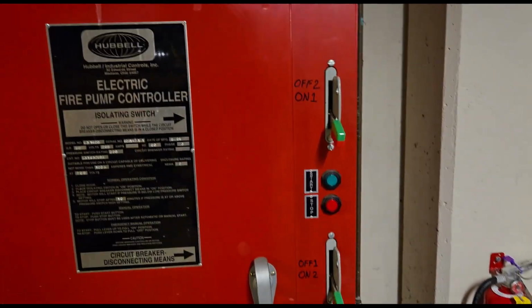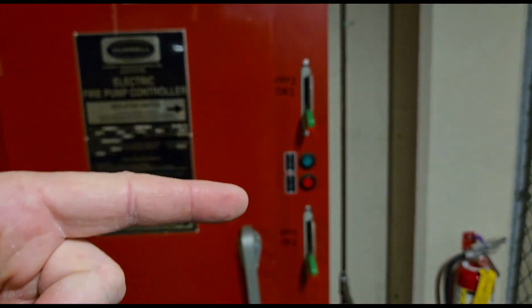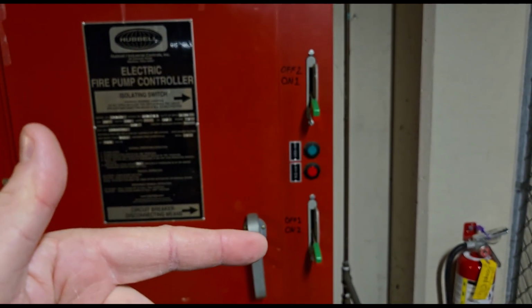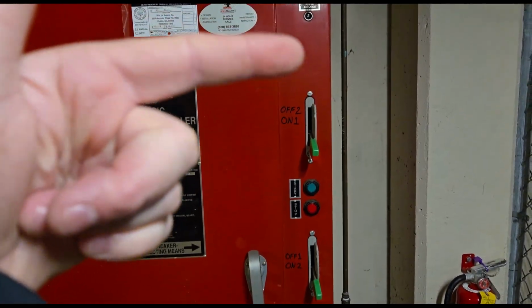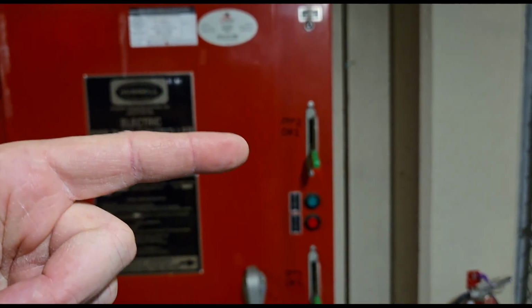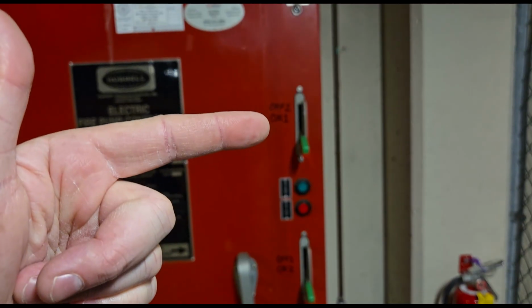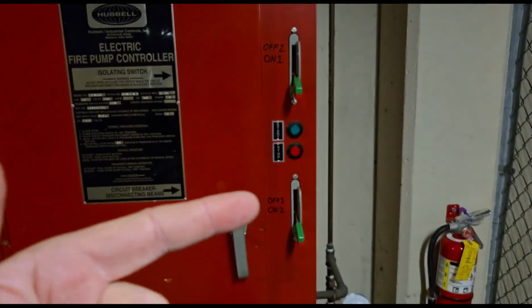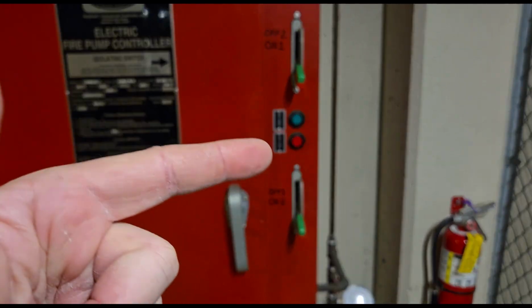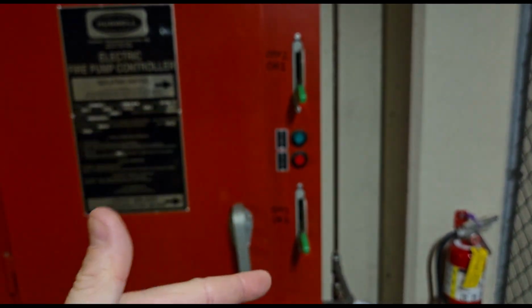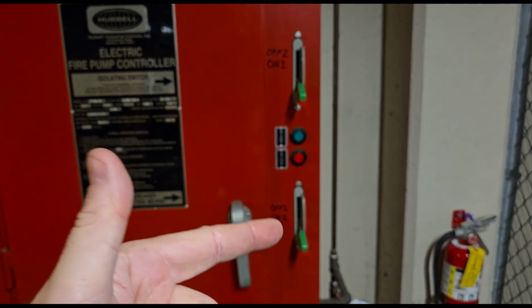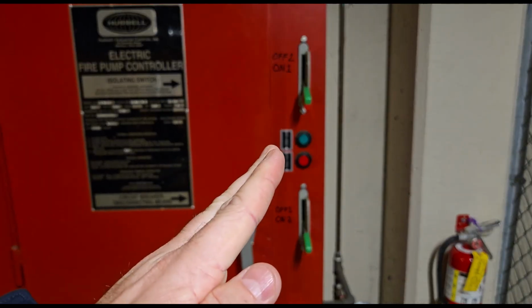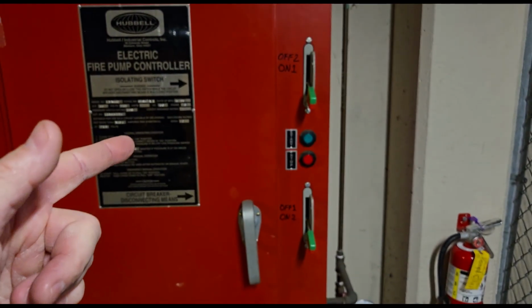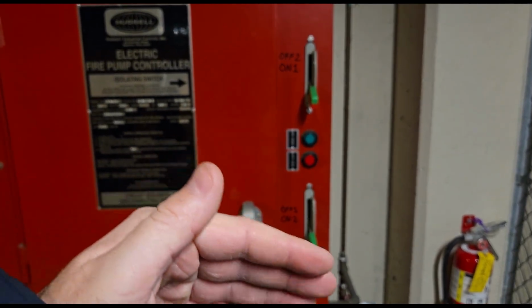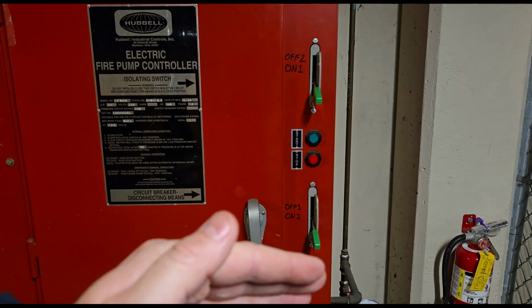But remember, we're going to go in the reverse order of these levers. We did off first for the circuit breaker and off second for the isolating switch. Now we're going to go on first for the isolating switch and on second for the circuit breaker, because you're not supposed to operate this isolating switch with the circuit breaker closed -- meaning the lever's up, meaning electricity is running through the system. We want the circuit to be open so there's no electricity running through it.